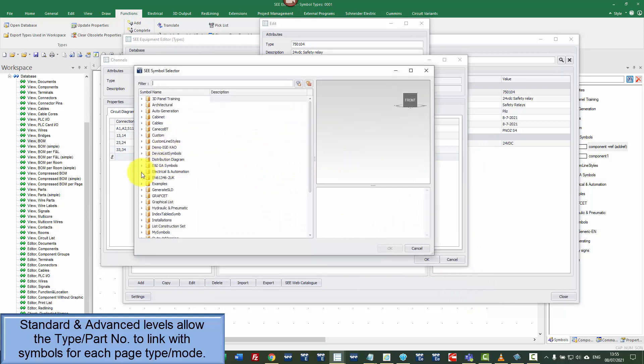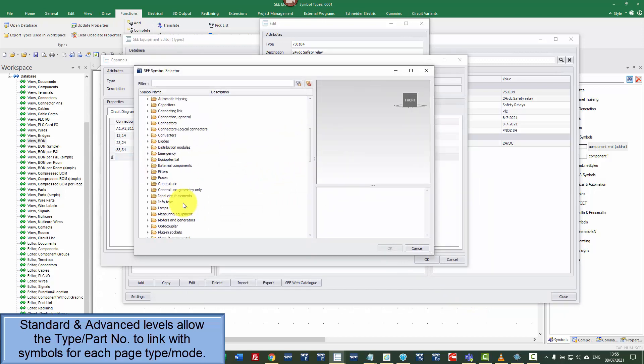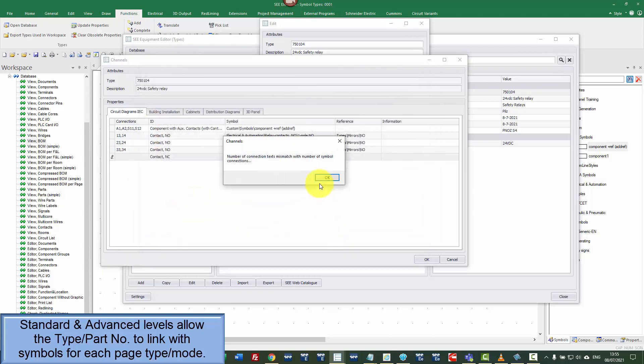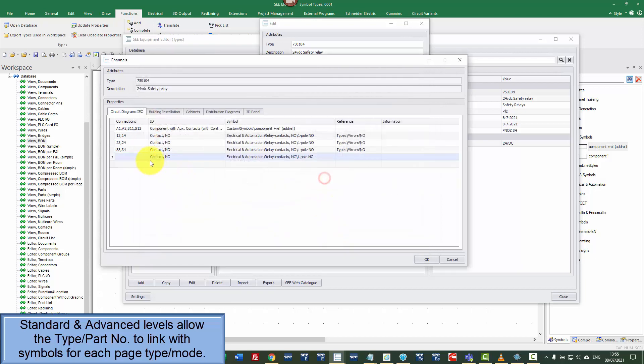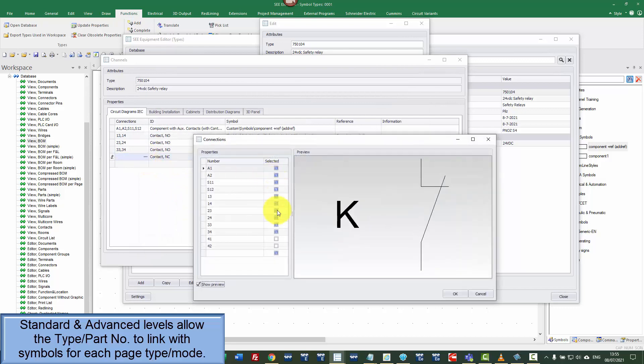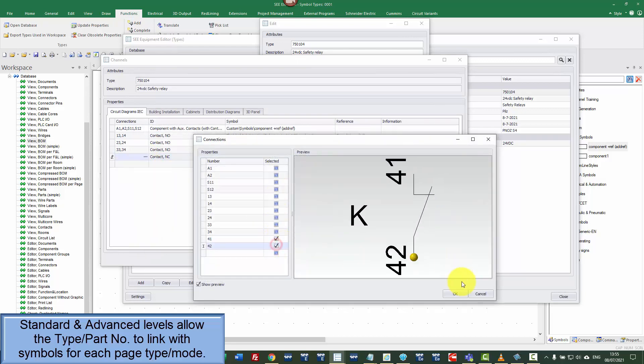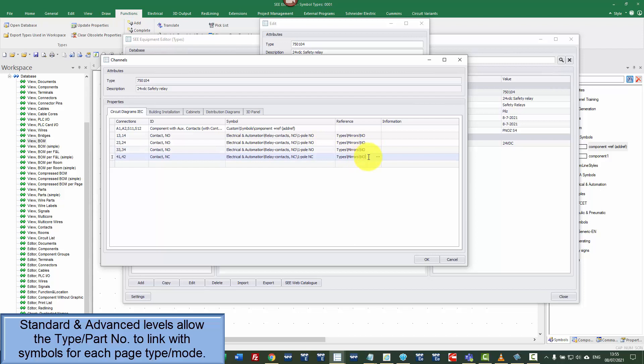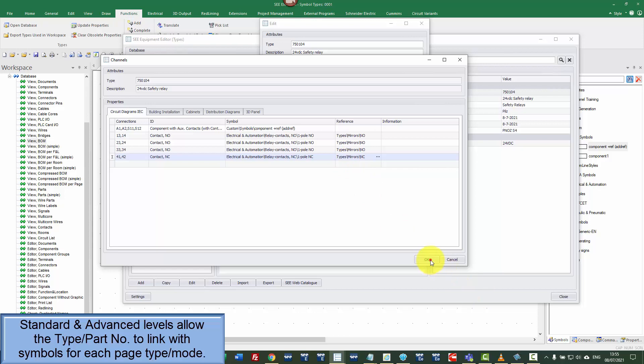I'm going to choose normally close contact for the last one. And again, in this case, actually, I'm just going to copy that and just change that to a C. So I've now defined that this is made up of a main symbol with four auxiliary contacts and each one of these has got a different reference defined. So I'm going to click OK, click OK.